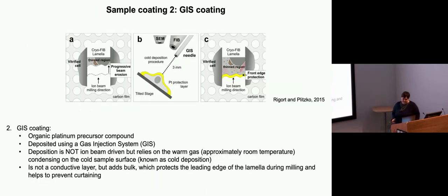Then the second type of coating is the GIS coating. GIS is the gas injection system. This is an organic platinum compound that's deposited. You have the needle and your sample is here and it basically condenses on the sample due to this temperature differential. In the case of what we're doing, for more room temperature work, people can also use the ion beam to actually drive the deposition. But this layer, it's not particularly conductive because it's not a pure platinum, it's this organic compound, but it's very useful in adding a protective layer.